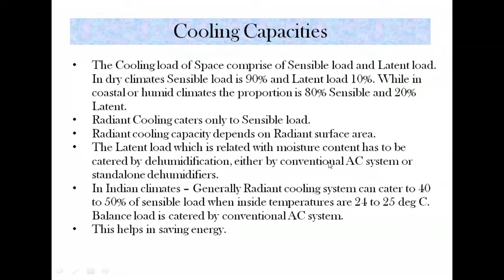So that is the reason I say our air conditioning systems, or the loads, we should be designing at higher temperatures to make it a sustainable model. We should not be designing at 22, 23 degrees C, because our outside temperatures are high. If you design at 22, 23 degrees C, then the person who is walking out of the air conditioned space, you are creating a thermal shock for him. It suits radiant cooling also, because your loads would come down, radiant cooling capacities would go up, your sizing would reduce, and you will be saving more energy. So this is all about the cooling capacities that can be achieved with the radiant cooling system, and I'll talk about how we can save energy with radiant cooling technology.